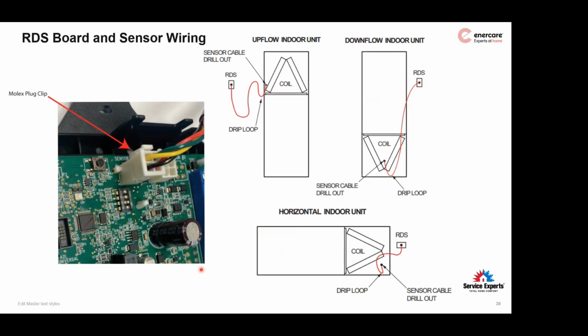Now, I don't recall seeing this in any other manual specifically. It doesn't mean it's not there, it just means I don't remember it. Lennox gives you this kind of wiring picture for their wiring harness for the sensor. It's showing a drip loop to prevent any possible moisture from coming down on the coil, hitting the sensor, running down the sensor wire, and into the RDS control board. Sensitive PCB doesn't really like water.